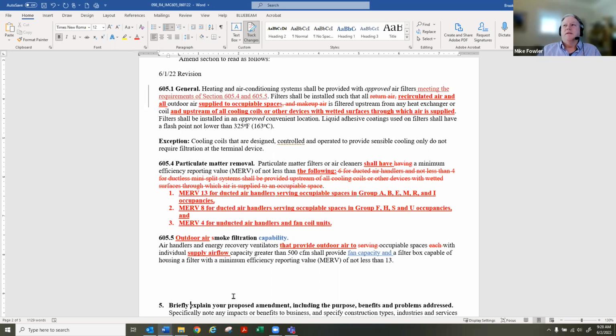Part of it is just aligning with what we currently have in 605.5, which has been approved by the TAG, and not trying to deviate from that as much. That was a new step added from City of Seattle language. I'm all for additional MERV 13 filtration, but I just felt that this was providing a good balance. Is a heat exchanger the same thing as an energy recovery unit? In fact, you're exchanging the heat. Yeah, it could have a wetted surface if it's a heat exchanger that has sensible only heat recovery and doesn't allow latent, so it could condense there.